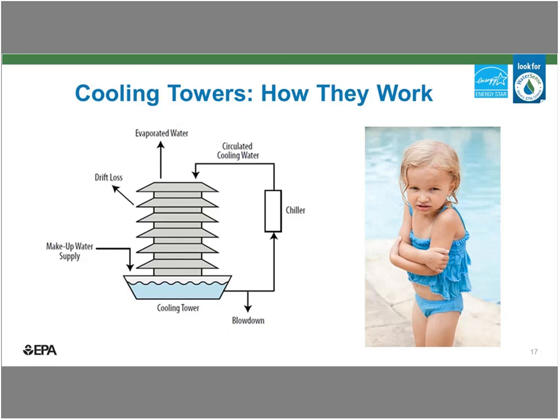If you ever feel that chill when you get out of the pool on a breezy day, even when it's hot out, that's evaporative cooling. And this is the principle that cooling towers use to remove heat. So there are some inputs and outputs from the tower that are of interest and will help with the next few slides. First, there's the circulated cooling water that is introduced into the tower to be cooled. This water is removing heat from a piece of equipment, in this case a chiller. Some of this water evaporates to remove heat.